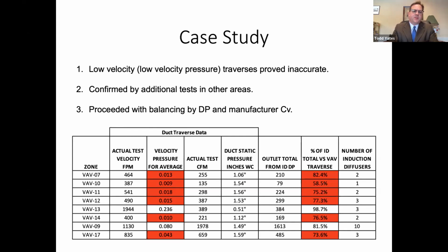And then we had only 2 in this set, VAV09 and VAV13, that were above that pressure. 9 was barely above it, but it had the added complexity of having 10 induction diffusers.